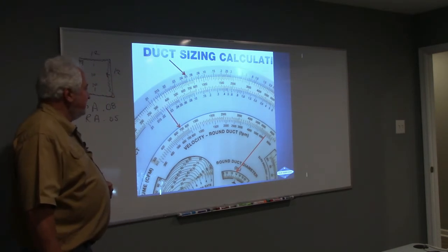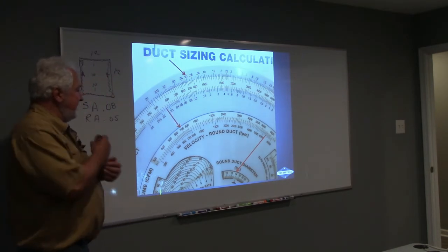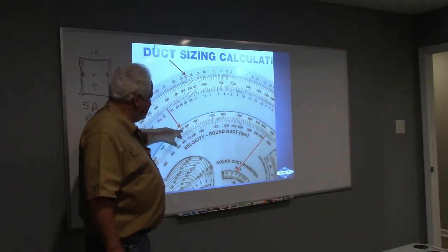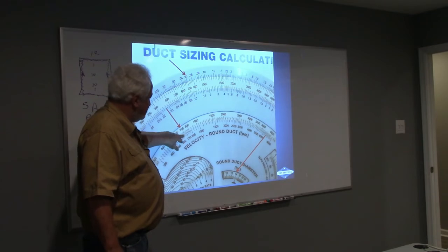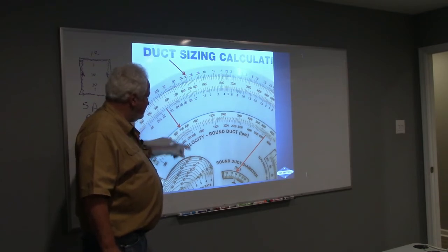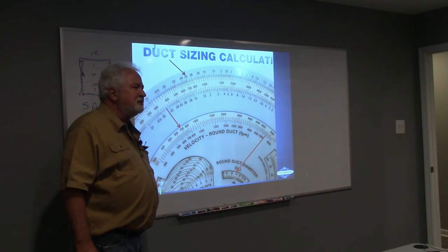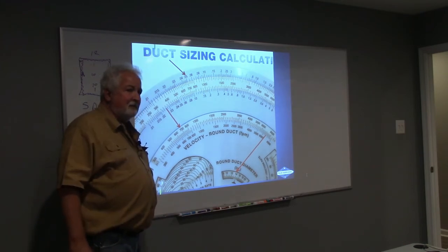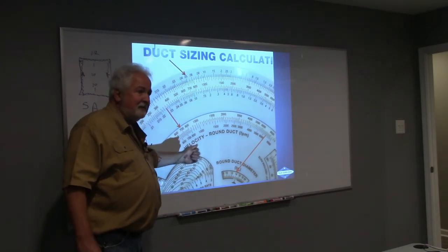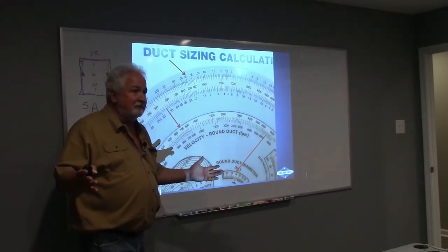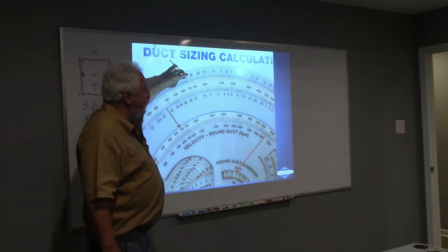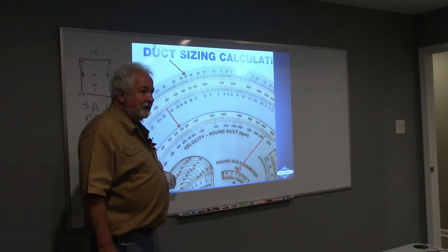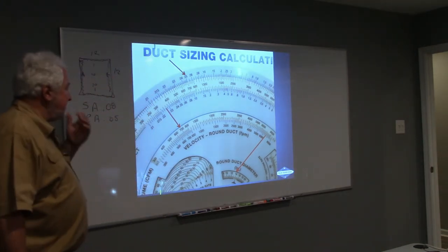700 times 2. But look at this. What's the speed of that air? We have 700 CFM, and what's going to be the speed of that air going through that return duct? 680-ish. How's that doing for our velocities that we were talking about earlier? We went 6 to 7. How are we doing? Perfect. So my world is good. But I had to get it down to 0.05, because if I was up at 0.08, that velocity would have been a lot higher. Okay? So that's why we went to that 0.05, good.